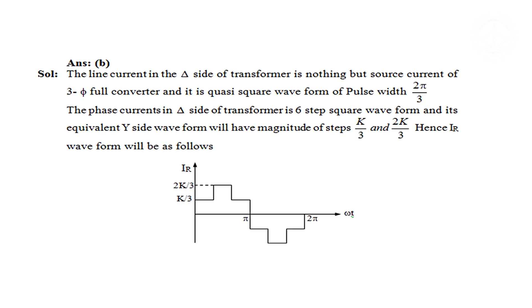Proceeding step by step, if you get the phase currents on the delta side, you will have a 6-step waveform with magnitudes of 1/3 and 2/3 per unit. From 0 to 60 degrees the phase current on the delta side will be 1/3 per unit, from 60 to 120 degrees it will be 2/3 per unit, and in the remaining half cycle it will be 1/3 per unit. Then, converting to the star side using the transformation ratio, you will finally arrive at option B.